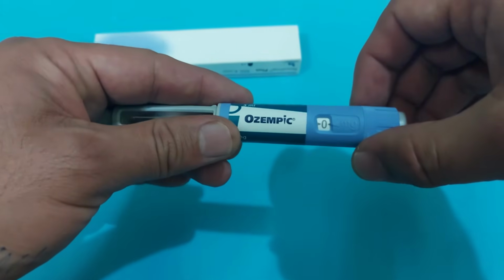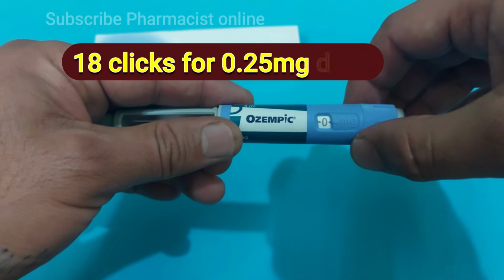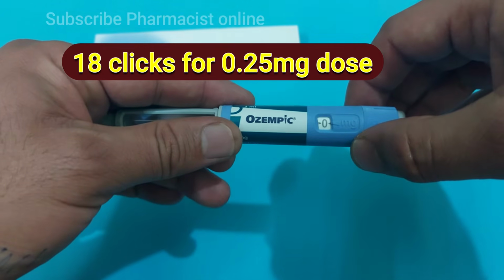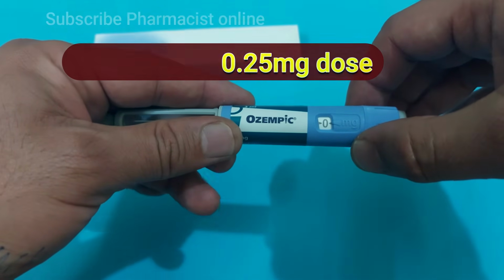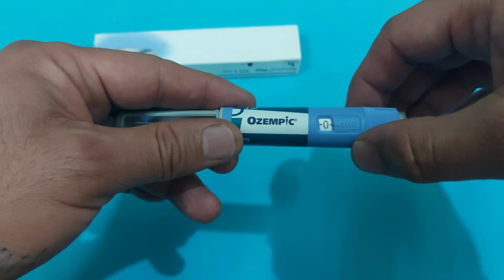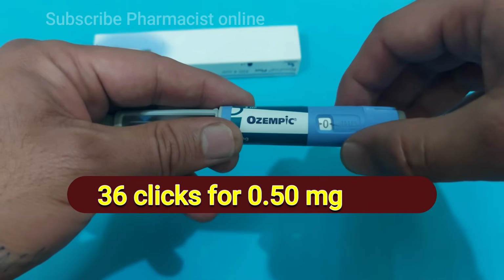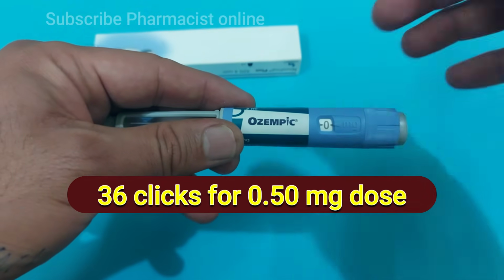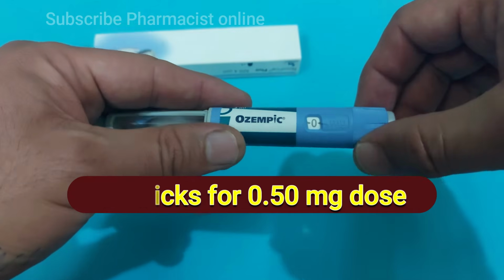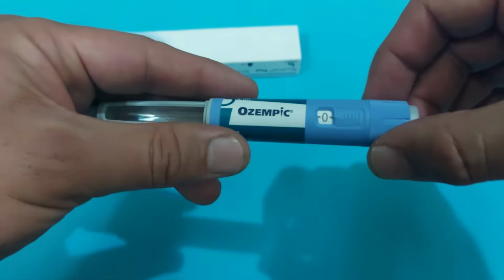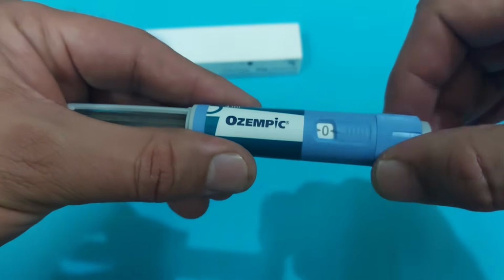As you can see, we need 18 clicks for the first 0.25 milligram dose, and for the 0.5 milligram dose we need 36 clicks, and the same goes for the other doses. So what you will do is count the clicks here.